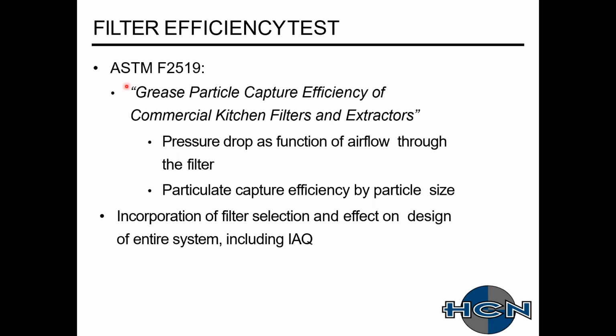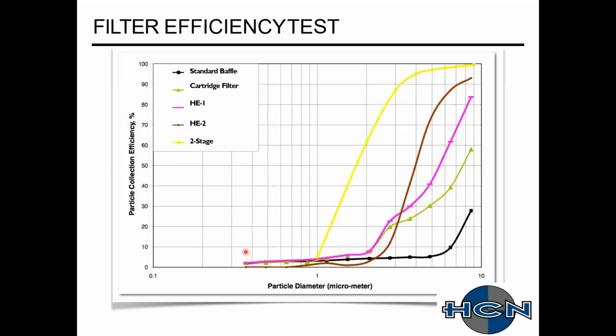So they actually came up with ASTM F2519, which is an efficiency test for filters. Back in the 90s and early 2000s when I started doing this, I would see standard filters or cartridge filters and they would proclaim that they're 90-some-odd percent efficient. They never dictated where that was on the graph. This is actually the test for ASHRAE, and they did it over a wide band of particulate. Your best filter for this would be a two-stage filter. So you'd have a standard mechanical baffle, and then your second would be a porous bead media. And those typically would capture the most grease.